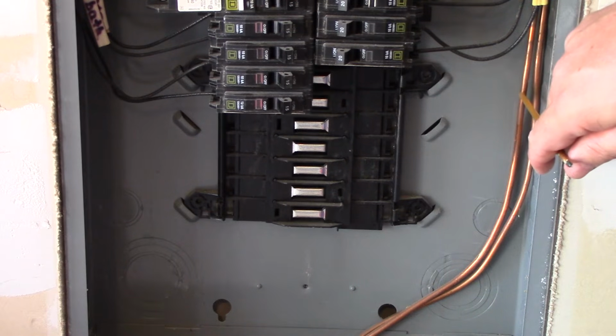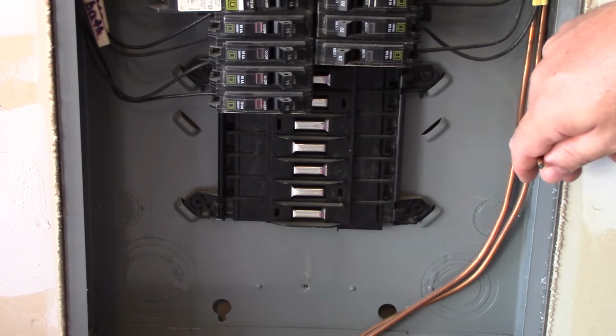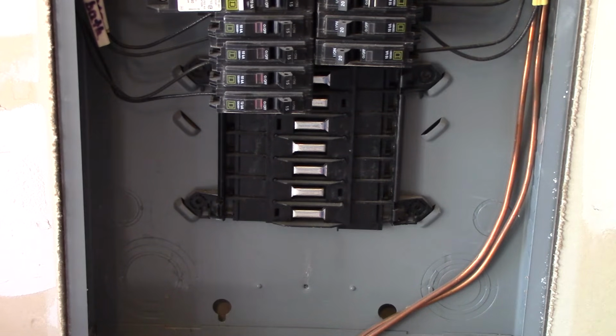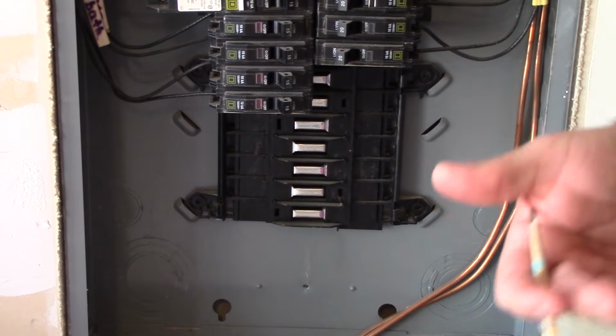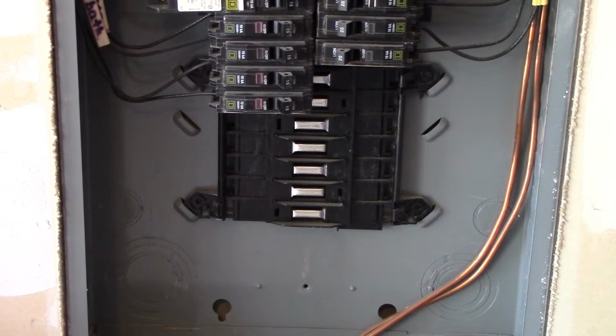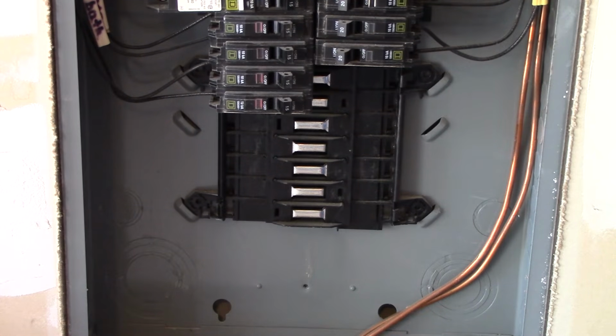Now, the other one they happen to run here, and I know it because I've seen it, and we'll look at it here in a second, is they actually ran it to a ground rod. Okay, so now for the ground rod, the code says in 250.66A that it doesn't have to be larger than a 6, because to be honest with you, that's all that a ground rod can handle. If it's driven 8 feet into the ground, if you can't drive it, then you're allowed to do it at a 45-degree angle. If that doesn't work, then you have to dig a trench 2.5 feet down, and then you're going to actually put it in that trench. Okay, but you have to make sure that if you have multiple electrodes out there, that they're at least 6 feet apart, and we'll look at that when we get out there.